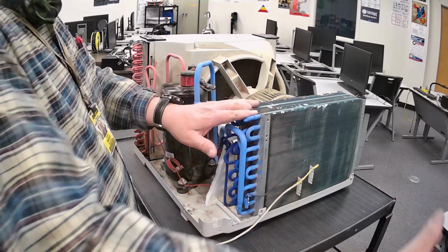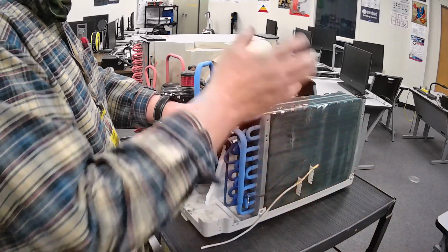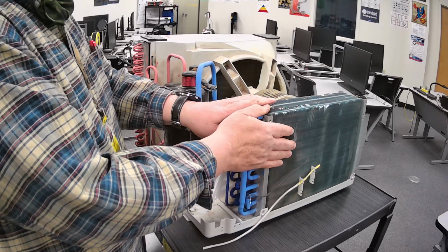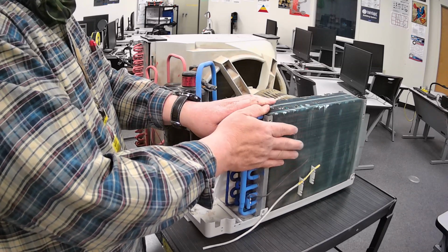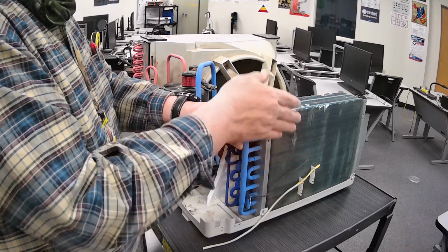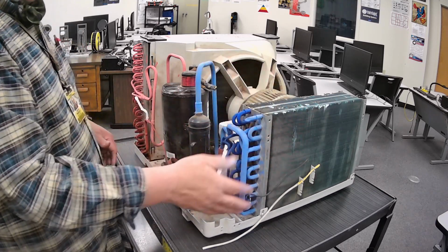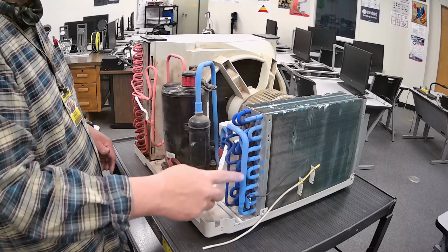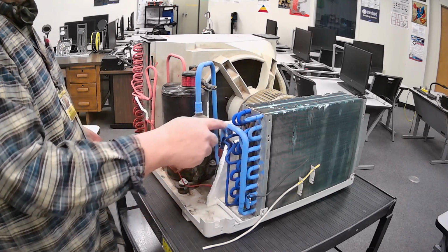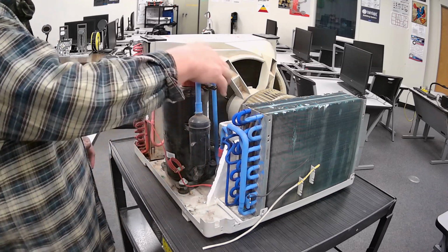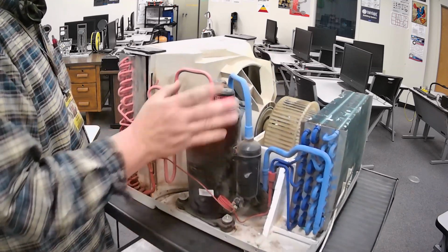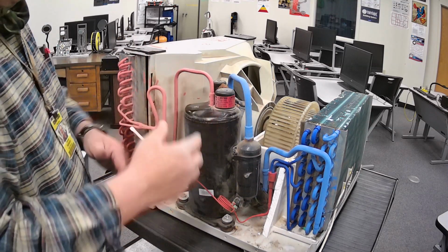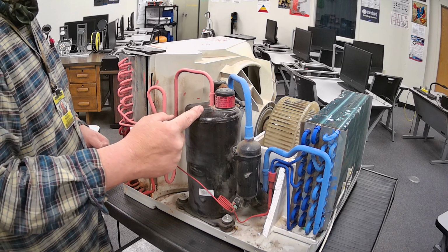So when that high temperature comes across it, that high temperature attaches to the evaporator. So the evaporator now transfers the heat from inside the house into the refrigerant. So now the refrigerant has it, and it turns the refrigerant into a vapor. Now the heat that's in the refrigerant goes into here, and then it takes that low pressure, low temperature vapor and compresses it, makes it a high pressure, high temperature vapor, comes out.